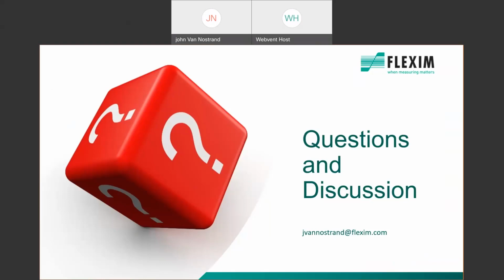All right, perfect. How does a FLEXIM meter, or any meter that measures velocity, account for fouled pipes when converting a velocity reading, what you measure, to a flow, what you want to know? Yeah, that's a very good question, and I can talk about that for quite a while. The short answer is there's no compensation for any meter that I'm aware of. You can't see the fouling on the inside of the pipe, so you have to deal with what you've got, and often that is a problem.